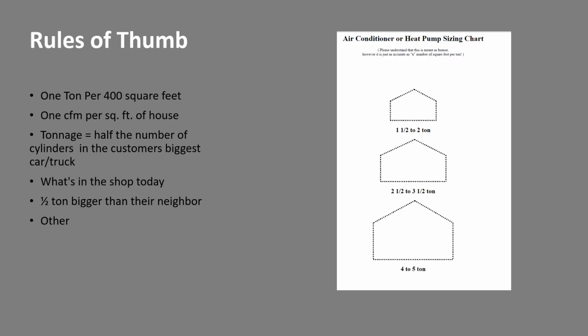Lots of rules of thumb exist out there on sizing. One of the famous ones is 1 ton per 400 square feet. And if that was ever right, it was not on today's homes. It was probably in a house with single pane metal windows, maybe R11 in the attic, nothing in the walls, nothing in the floor, and probably a really leaky house. Other folks like to size using 1 CFM per square foot of house. Hopefully later on today we'll talk about why sizing by square footage is not such a good idea.